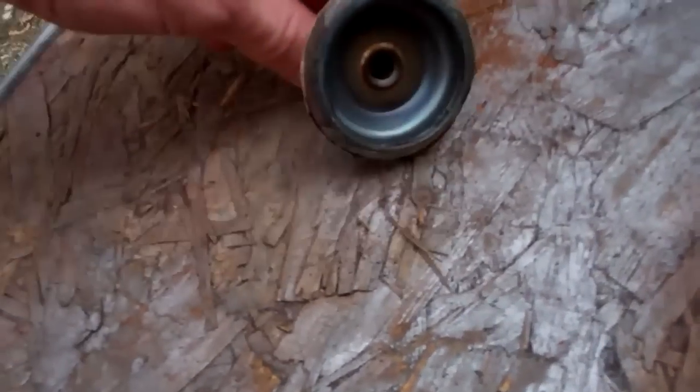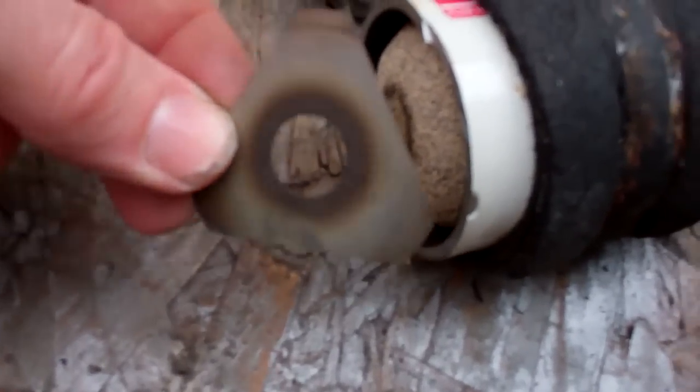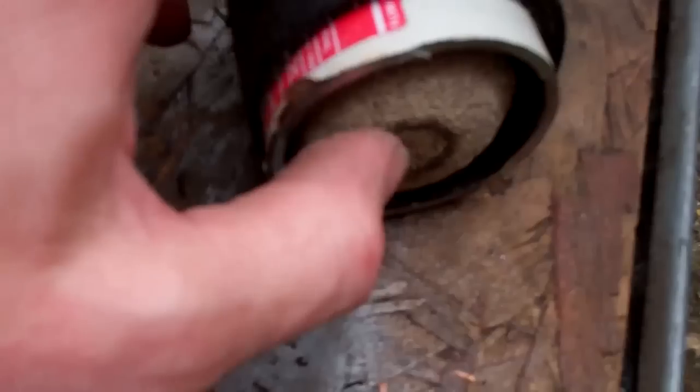This is an older style Danfoss dryer. I used to paint them white. It's still hot from grinding. We've got a little triangular disc spring to give that a bit of tension. Just tapped it and there's a load of little coppery bits that have come out of there - obviously from when it was piped up.